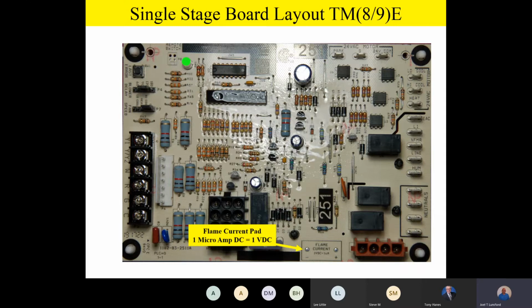So now you don't have to have a special flame current meter like we used to have in the old days, where you'd have to pull the flame sensor wire off and hook your meter in series and all that stuff. We don't have to do that anymore. So with all of our Champion furnaces, we have a flame current pad, and it allows you to take just a plain Jane voltmeter, which you're going to have on your truck anyway, and go to DC volts and read DC volts between those two terminals.